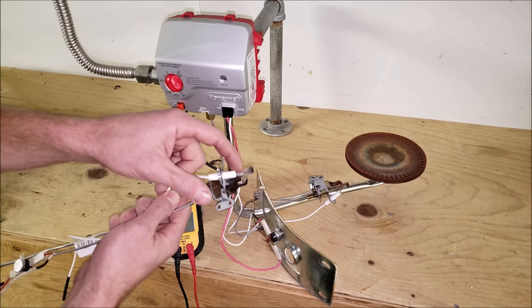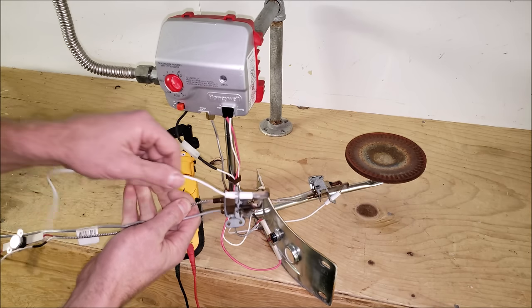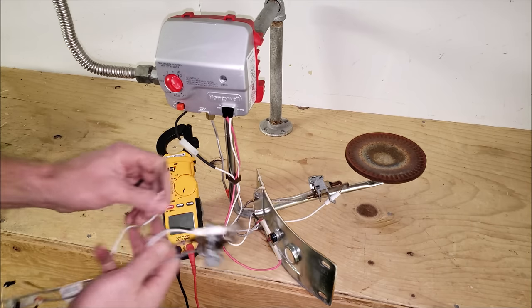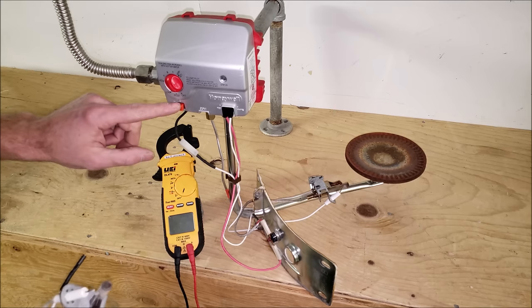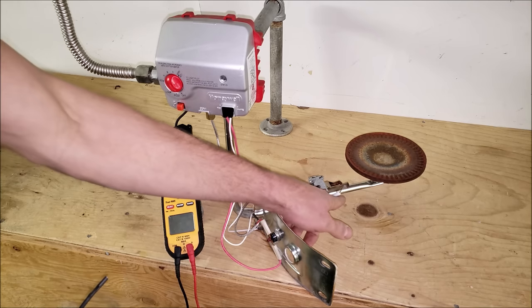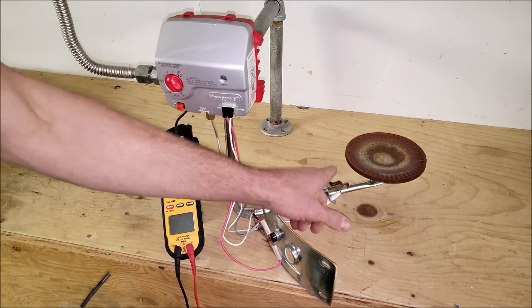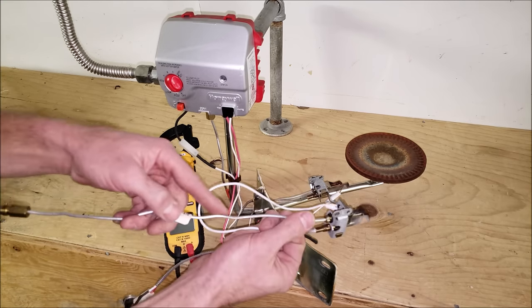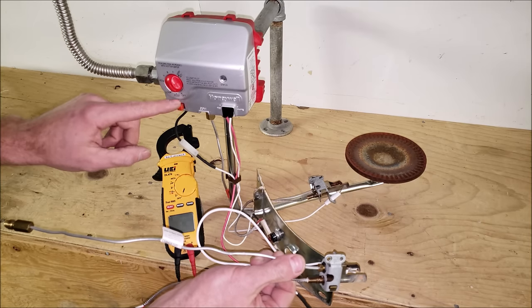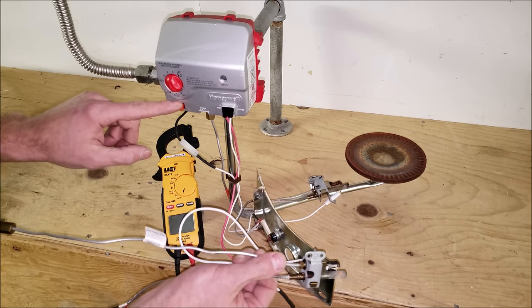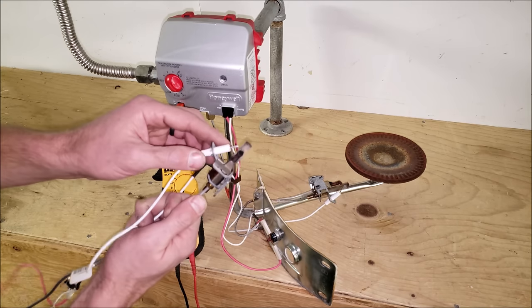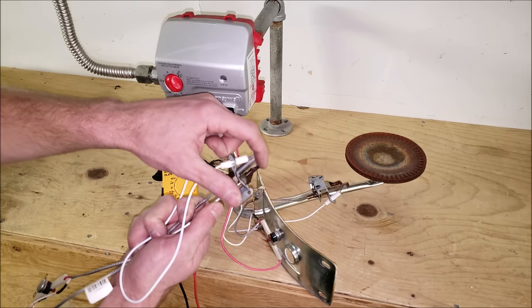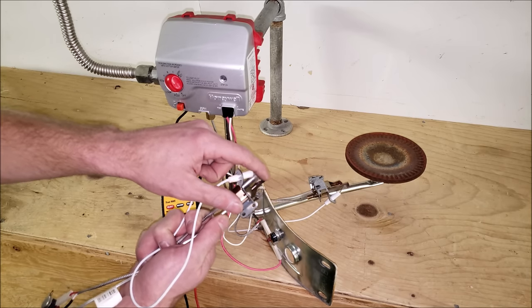This is just a stainless steel rod surrounded by the ceramic and then you have your wire coming through that connects over to your piezo lighter. It just comes from here, goes over to the spark igniter and jumps across to the closest ground and it comes back through the pilot or basically on the pilot tube because that's the ground back over to the igniter to complete the circuit. So it's creating high voltage and sparking across over to the thermopile or the flame termination head and that's what's going to ignite your initial pilot gas.